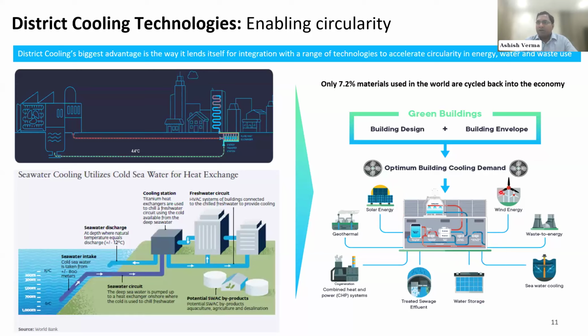We can also integrate wind energy. We can also integrate waste to energy plants. Seawater cooling is something we have done, one plant. I have this example on the left-hand side of how seawater cooling operates. Then obviously the water storage, whether it is thermal storage, chilled water based, ice-based or PCM-based. The most important integration of district cooling is the utilization of treated sewage effluent. This sewage STP water, when it is treated, is normally discarded. If I give you the example of the Middle East, it's normally discarded. And district cooling plants can utilize this water, which can help us reduce the dependence upon potable water or fresh water.